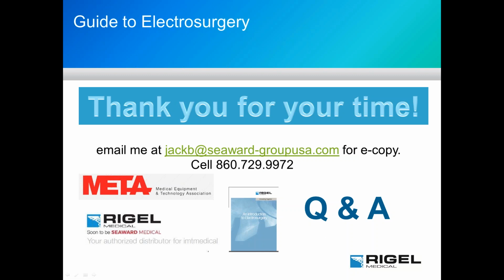Here's a new one. How long does it take to do a PM? With our test sequence, doing the full test, all of your high frequency leakage testing, all of your cross coupling testing, I've completed the PM test sequence in 45 minutes. If you're doing it for the first time, it's going to take a little bit longer because you're going to be double checking your connections, that you have your foot switch adapters in place and the cables going from the front of the Unitherm to the correct foot switch adapter, which is always a mistake I make. But once you're up and rolling, you should be able to get it done in 45 minutes.